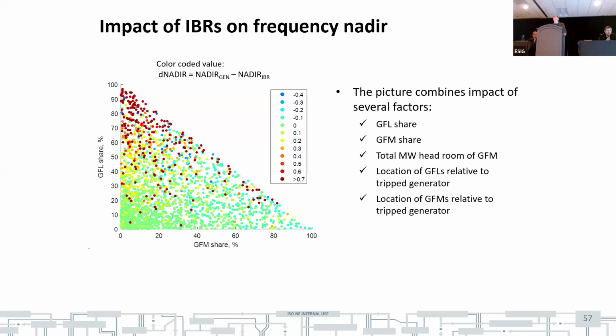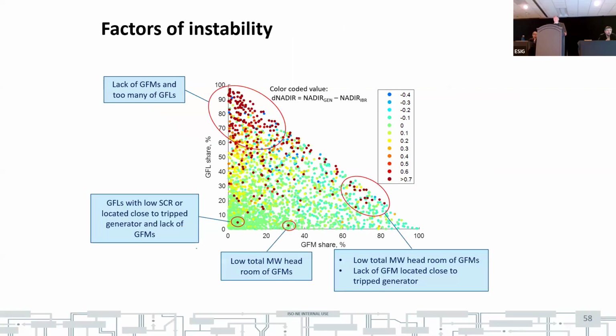And the reason for that is because that is a two-dimensional graph showing results of approximately four-dimensional results, when you see different penetration of IBR, different headroom, and different allocation across the system. So that graph roughly explains the main trends, what is happening in the system. For example, on that area, on the top left part, a lot of red dots, and that means it's a reflection of the pattern when you have a lot of grid following inverters and lack of megawatt headroom for control in grid forming.